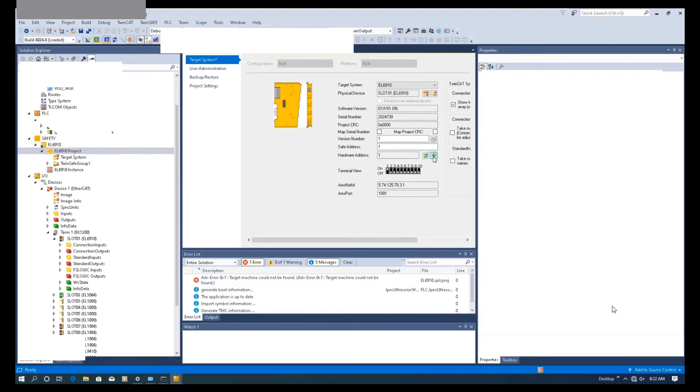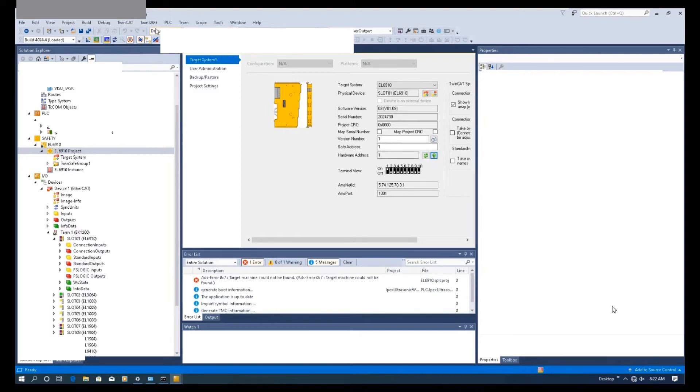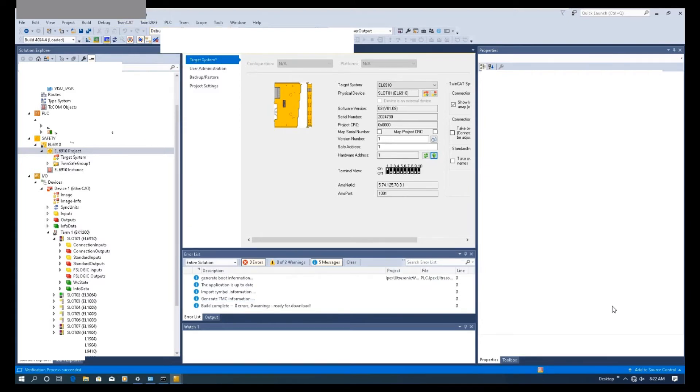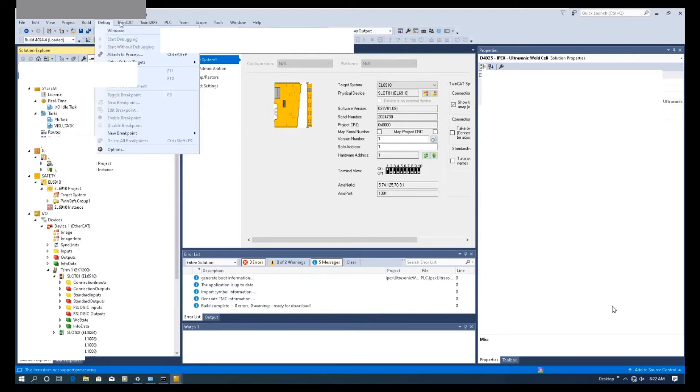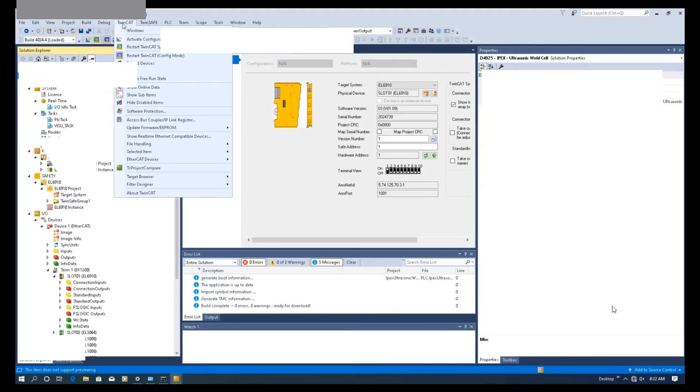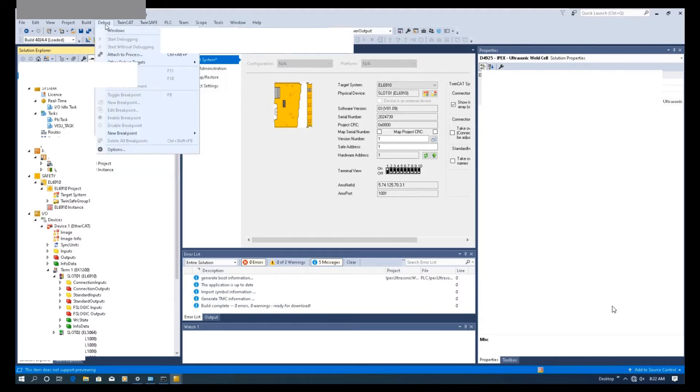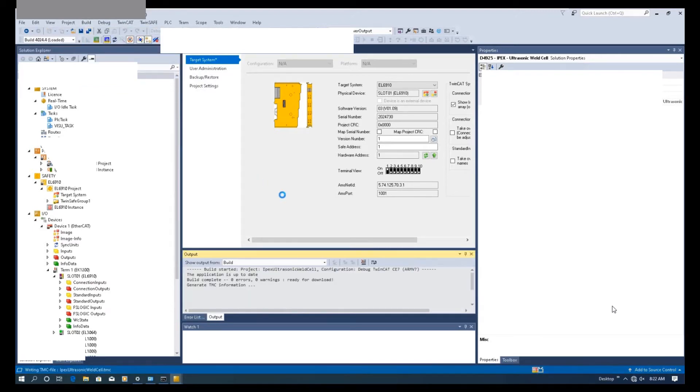We can use this to toggle free run mode status. You can click this arrow to upload the actual hardware address. After that, if you click compare the safety logic, there will be no errors pop up again. Once we get this actual hardware address and compare the path, we can switch the system back to run mode.